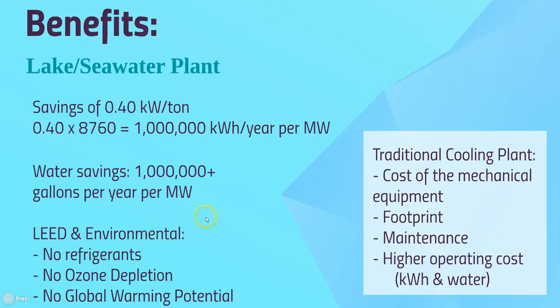So definite benefits there. Now, if you're leaning more towards the financial, you're going to want to point out to, say, a developer or owner that, hey, if we're using a river, sea, or lake plant, we don't have as much mechanical equipment, so we're saving on the cost of the mechanical equipment, the space for that mechanical equipment, and then the operations and maintenance of that mechanical equipment. So we're avoiding all of these aspects, plus we have a lower operating cost overall. So kilowatt hours and water overall for the entire cooling plant.